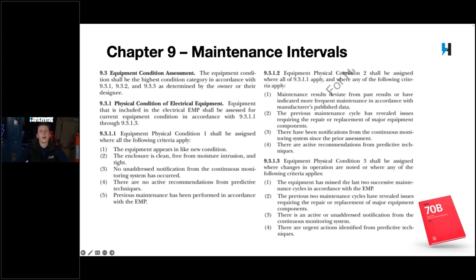Even if it hasn't caused a problem, if you've missed two consecutive maintenance cycles, which depending on what it is could be a few months or even a year, then it's every 6 months at that point. If there's been some major issue or replacement, unaddressed issues in the system, and you're running around putting out fires, you're probably looking at condition 3 equipment. You need to do it every 6 months until you can get it down to a 2 or a 1 as far as its reliability.